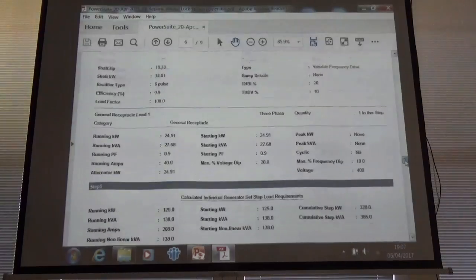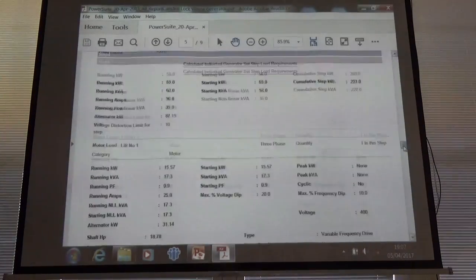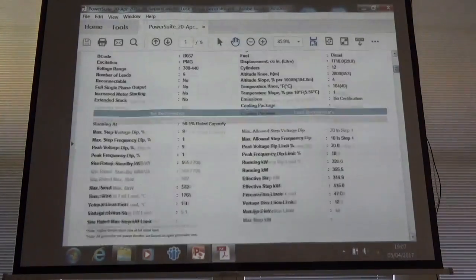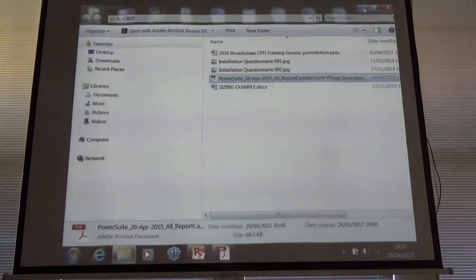So there are programs that will certainly assist you in doing that, but then you've still got to apply the criteria or the consideration. If you're starting those systems, how long do you want them to run for? What's your cap on the actual total amount of running time you expect per year? Is that going to be a straight load, or is that going to be a variable load? Now that in turn impacts on what you need to do with keeping it within the rating framework.